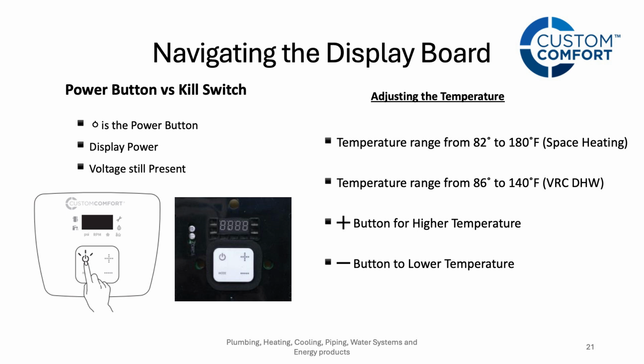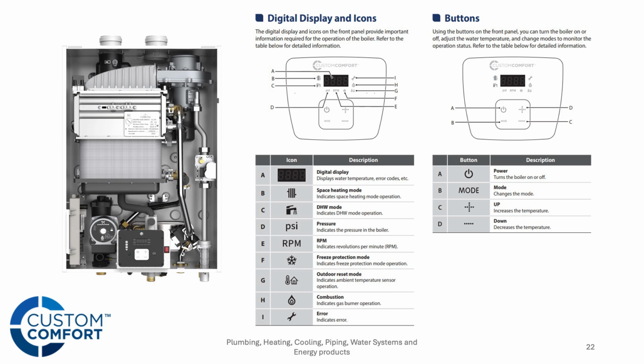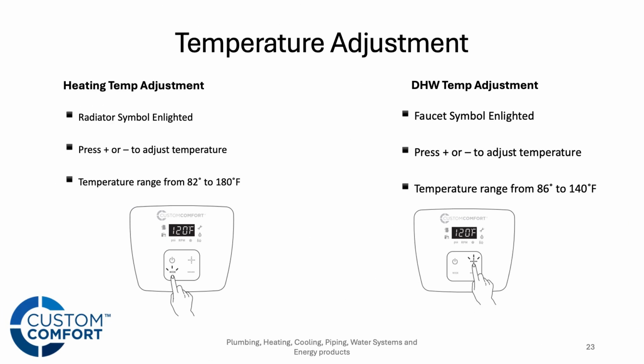When you go through the modes in setting up the boiler with that display, we're going to hit the mode button until we find what we're looking for. We hit the mode button and wait for the radiator to be highlighted to set the heating temperature. If you're using the outdoor sensor, that's probably going to dictate a majority of that. But if you're not using it and you want to hook this up at 180 degrees for baseboard, you do that via the radiator symbol on the control board. On the combi, to set the domestic temperature, we hit the mode button until the faucet is highlighted, and we set the temperature we want there. Those are the basic parameters you can adjust from the front end of that control.